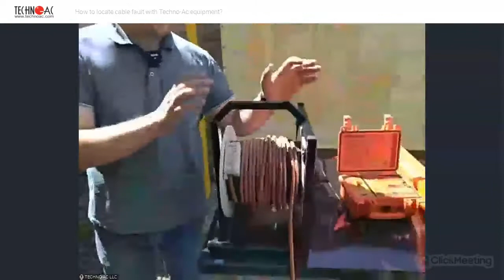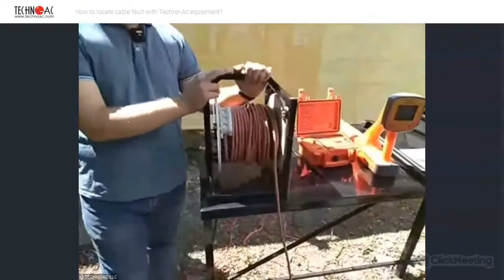First of all, I would like to show you our test field for today's event. This is a barrel with 150 meters of cable. It's a four core cable. Each core is split here on this side, and each core represents a particular fault of this cable. We have simulated several faults on this cable, and we will be using TECHNO-AC equipment today to test if there is any fault, and we will be able to locate them.